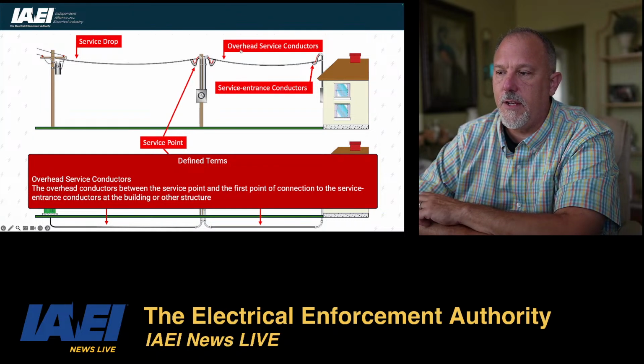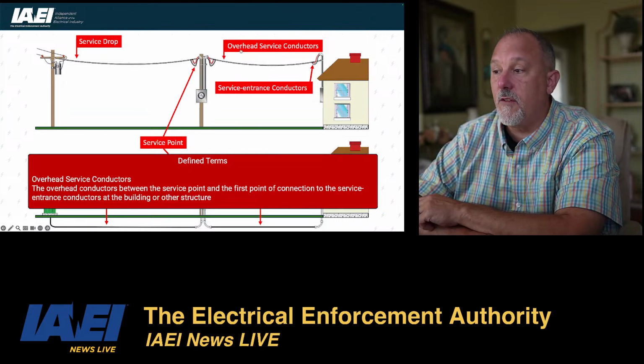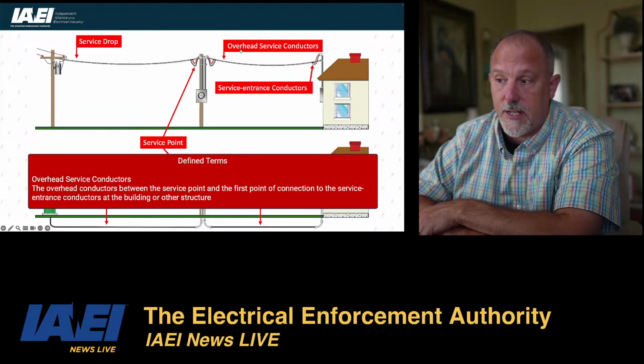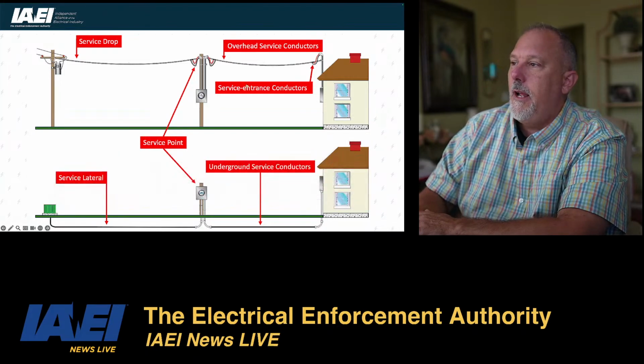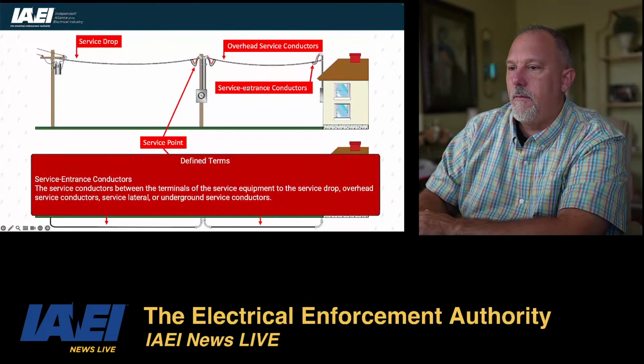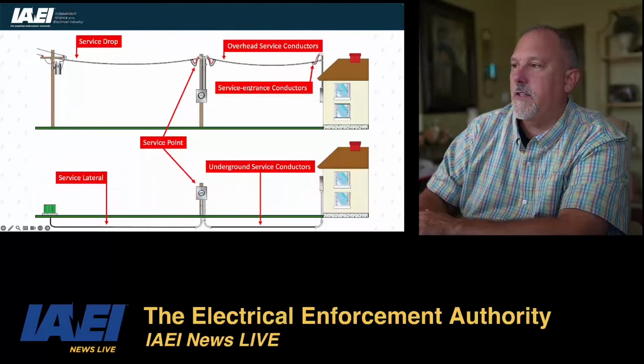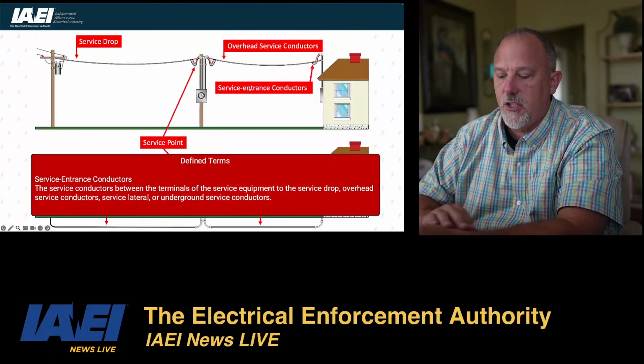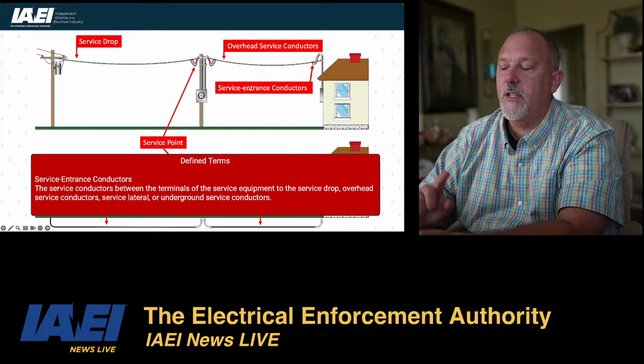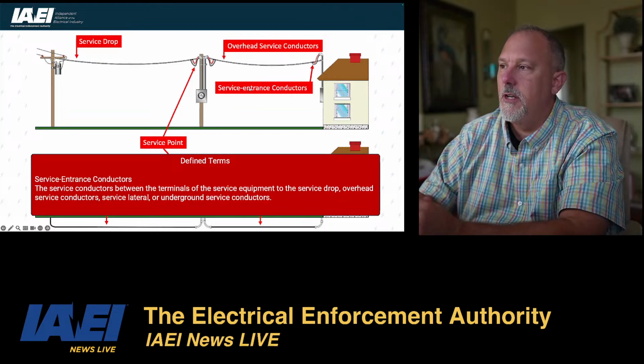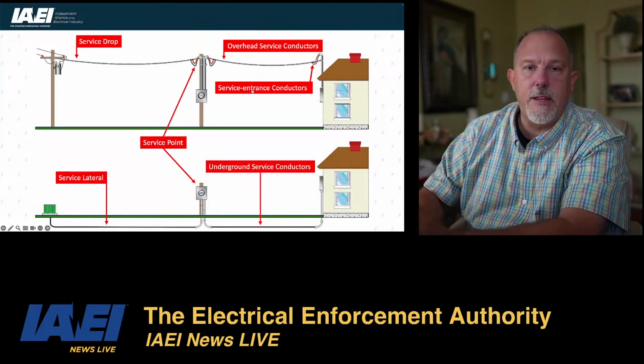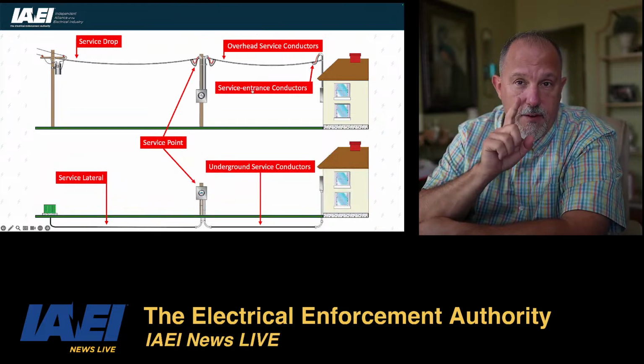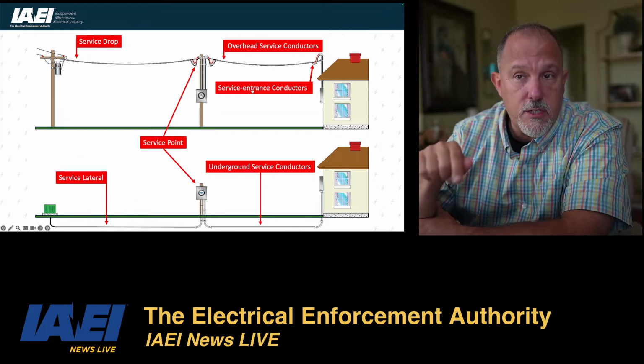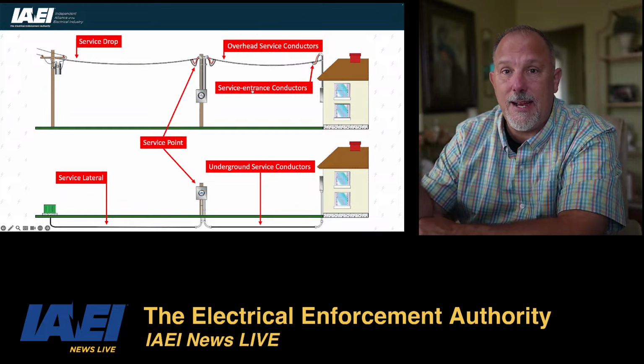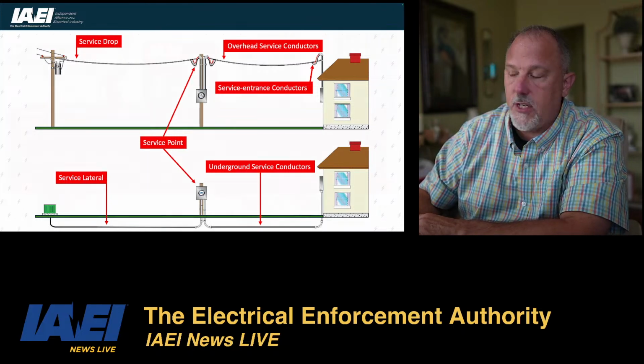The overhead service conductors, the overhead conductors between the service point and the first point of connection to the service entrance conductors at the building or other structure. Those are your overhead service conductors. These are your service entrance conductors: service conductors between the terminal of the service equipment to the service drop, overhead service conductors, service lateral, or underground service conductors. That's a very important term to remember and a very important part of the power distribution system for you to recognize, because that's where you're going to be tapping in for your alternative energy equipment. Thank you, David.